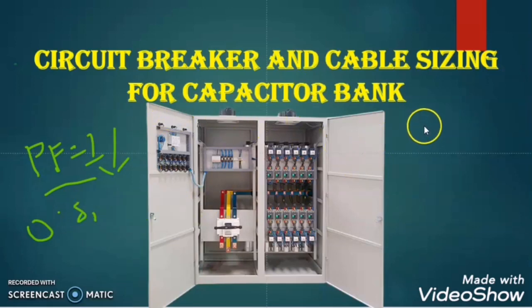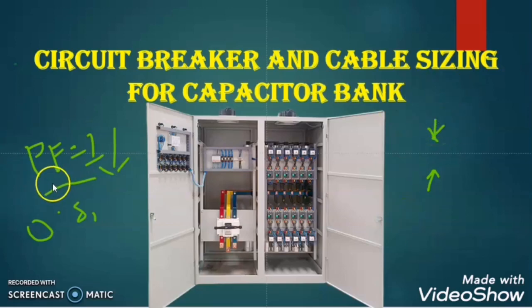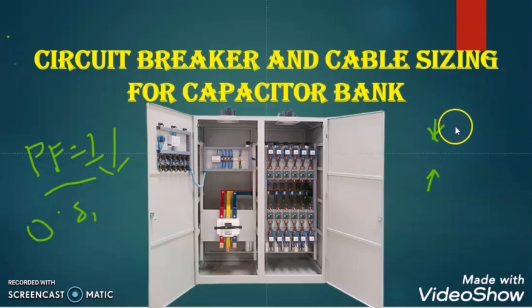As the inductive loads are lagging in nature, if we add some load which has leading nature, then the leading load will compensate with the load having lagging nature. In that way the power factor of the electrical installation will improve. All inductive loads have lagging nature and the capacitive loads are leading in nature. So the trick to improve the power factor is that wherever there is more inductive load, we add the capacitive load in order to compensate it.